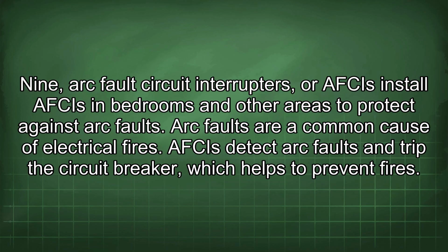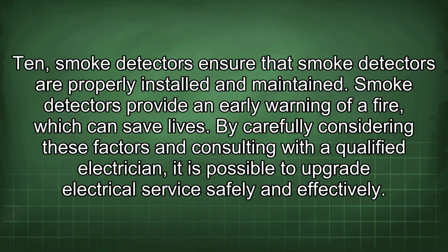9. Arc fault circuit interrupters, or AFCIs. Install AFCIs in bedrooms and other areas to protect against arc faults. Arc faults are a common cause of electrical fires. AFCIs detect arc faults and trip the circuit breaker, which helps to prevent fires. 10. Smoke detectors. Ensure that smoke detectors are properly installed and maintained. Smoke detectors provide an early warning of a fire, which can save lives. By carefully considering these factors and consulting with a qualified electrician, it is possible to upgrade electrical service safely and effectively.